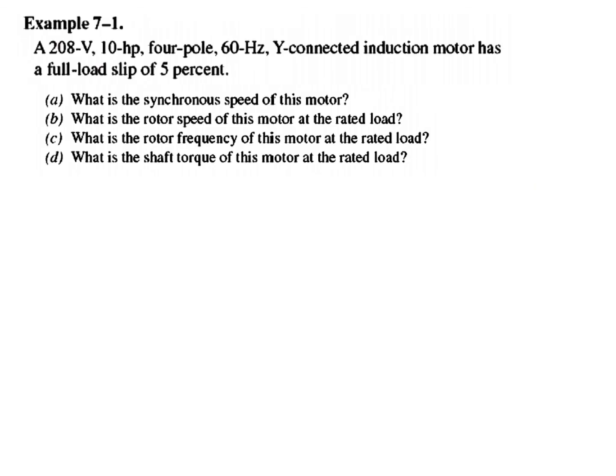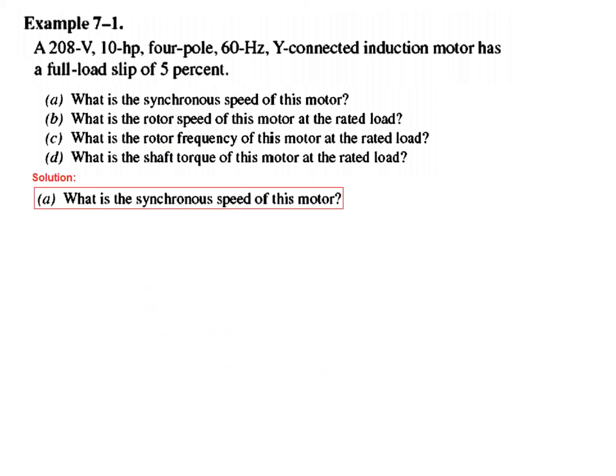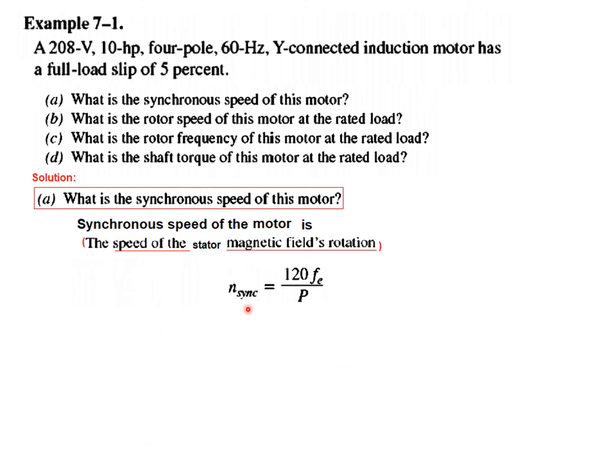Let's solve an example. A 208-volt, 10 HP, 4-pole, 60 Hz, Y-connected induction motor has a full-load slip of 5%. We need to find the synchronous speed, rotor speed, rotor frequency, and shaft torque. For the synchronous speed, using N_sync = 120 f_E / P: with f_E = 60 Hz and P = 4 poles, N_sync = 120 × 60 / 4 = 1800 RPM.